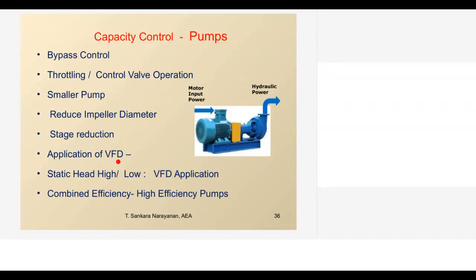So already certain questions on VFD, we will discuss that. VFD will be predominantly required, like what we are telling, normally if you put a 500 liters per hour pump, how much will be the variation in industry? The pump is designed for 500 liters per hour. Normally, industry will vary the flow from 500 liters to up to what level? 30%, yes. See, most of the time, because we can't run a plant at 10% load and 100% load, even if there is a variation, the utilities will operate between 70% capacity to 100% capacity. In that case also VFD can be considered.